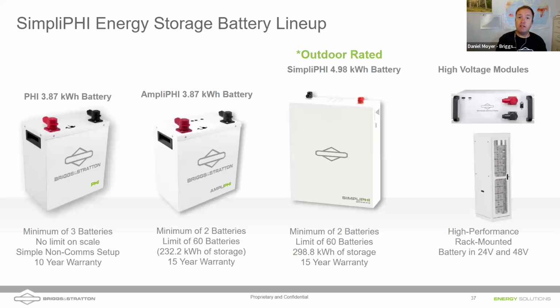These are some of the legacy batteries that we've been doing, right? The Phi on the far left makes a great lead acid battery replacement. It doesn't have closed loop comms, but if you've got an older piece of equipment, an old Outback, Schneider, right? You don't have comms, leverage that. Additionally, the SimpliPHI battery is there, outdoor rated 4.98, and those are the high voltage batteries that would be used on some of the Solarc 30K and the 60K.